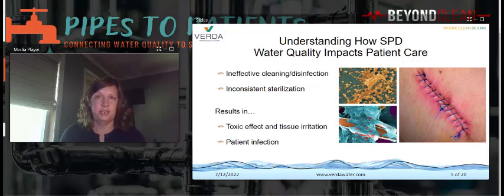Ineffective cleaning, disinfection, and sterilization can ultimately result in adverse effects on patient care. So too if bacteria or endotoxins are present in the final rinse water during instrument reprocessing. If there are high levels of total organic carbon, for example, this acts as food for bacteria and promotes bacterial growth. Bacteria and endotoxins on an instrument just sound bad, but what are the ramifications for patient care? For one, toxic effects. Tissue irritation can result from residuals on a device or implant that was reprocessed using water of inadequate quality.